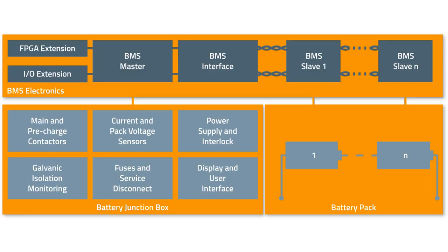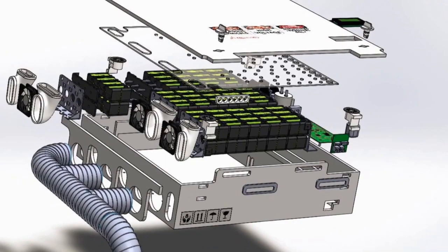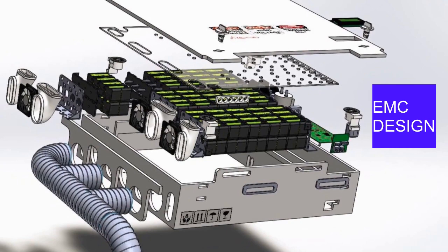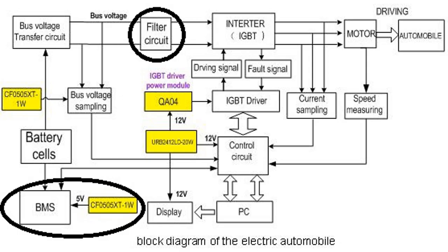EMI can be a problem if not given appropriate care. In general, all sensors are vulnerable to EMI. In the worst case, sensor acquisition could be distorted only slightly so that the BMS master is unable to identify false measurements. The other extreme condition would result in complete uselessness of data points, but at least it would be detectable. To reduce this influence, electric machines, power electronic components and other loads have to be designed well regarding EMI.